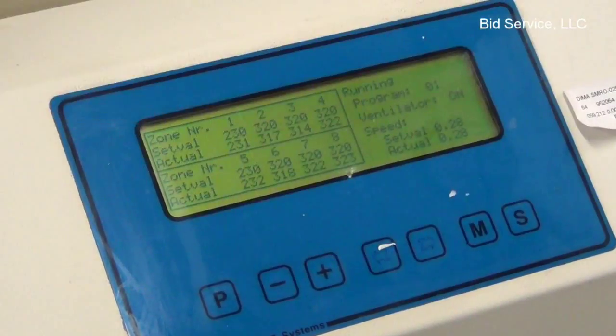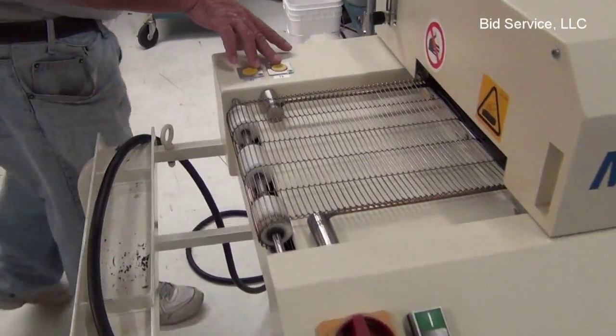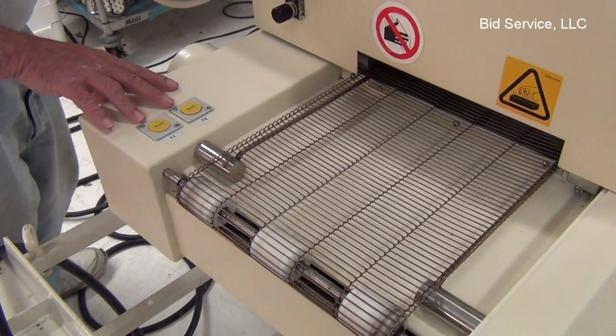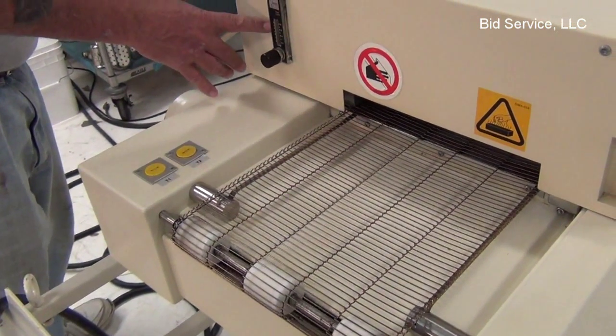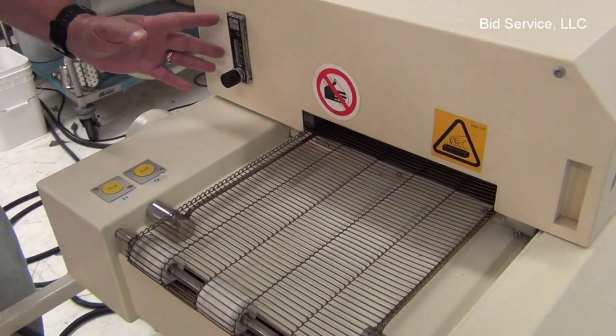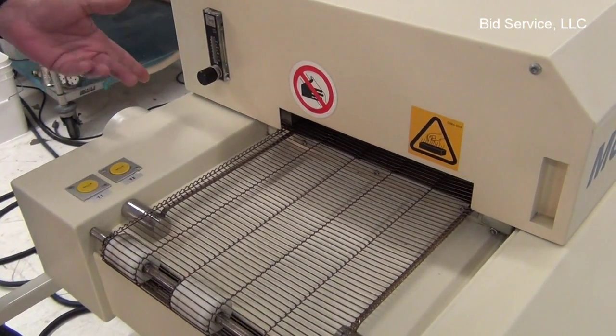Going around the side here — this is where you could enter your own thermocouples, have them plugged in to do that measurement mode. There's a connection on the back here for the flow controller; this is if you wanted to add an inert gas so that it's flowing as best as it can over the boards to keep oxygen off there and maintain room atmosphere.